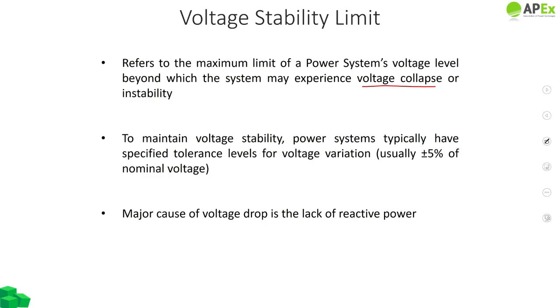Okay, to prevent the system from ever reaching such a point, the grid codes prescribe certain tolerance limits in which the voltage can be maintained for stable and reliable operation. These limits are usually plus minus 5% of the nominal value. So in per unit we can allow the voltage to rise up to 1.05 per unit and drop down to 0.95 per unit of the nominal value. But these grid codes also, in emergency circumstances, permit a certain higher band, which is called the contingency voltage band, in which the voltage can rise up to 1.1 pu and fall down to 0.9 per unit.